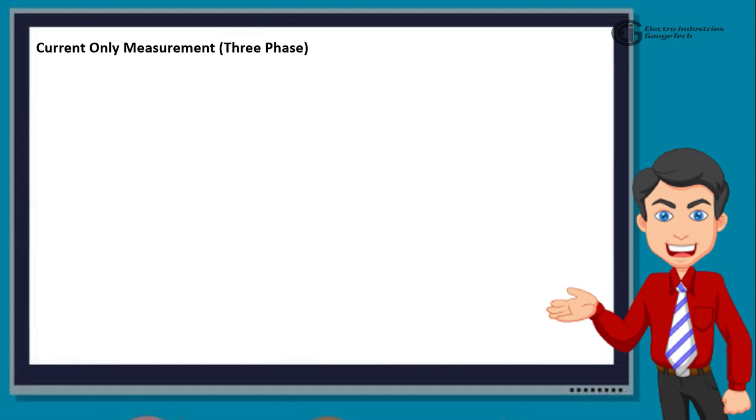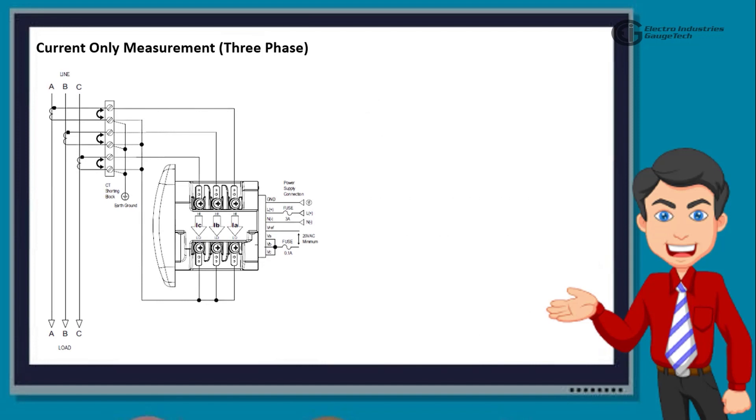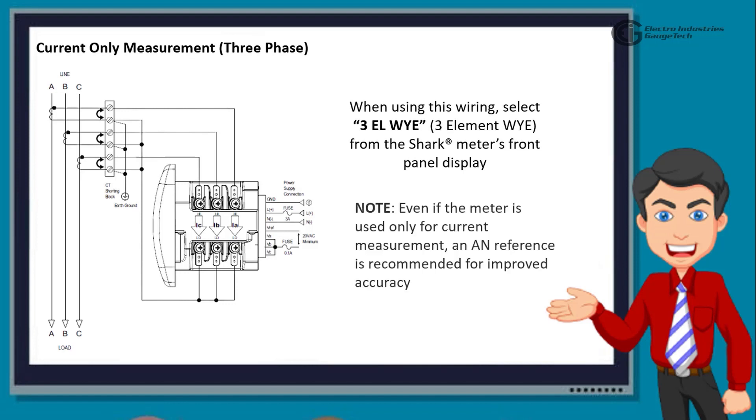The next diagram is for the current-only measurement, 3 phase. When using this wiring, select 3 EL WYE from the Shark Meter's front panel display. Note that even if the meter is used only for current measurement, a reference is recommended for improved accuracy.